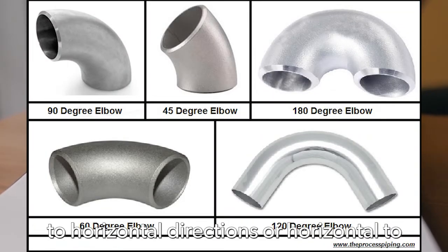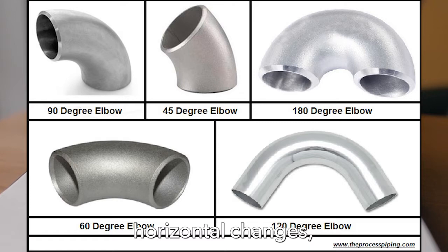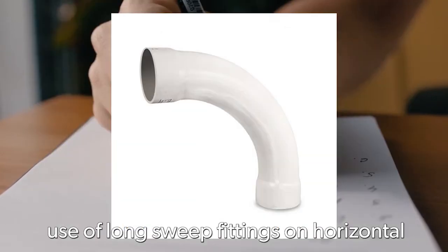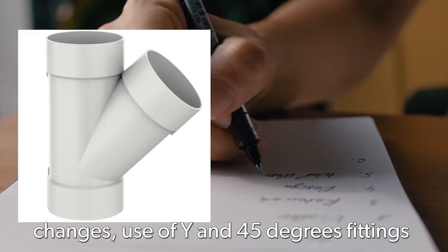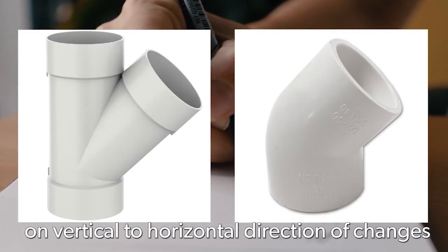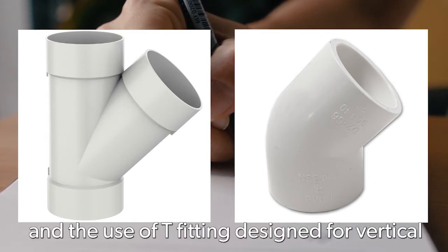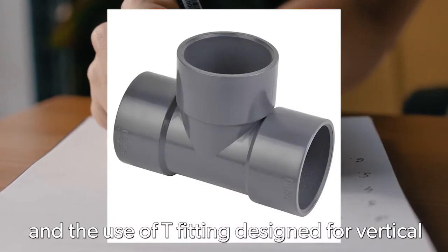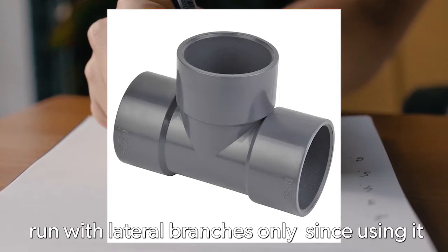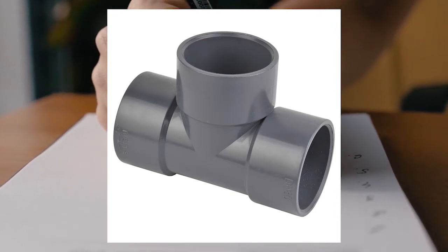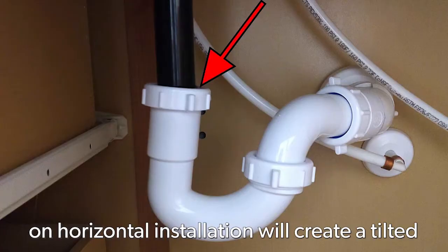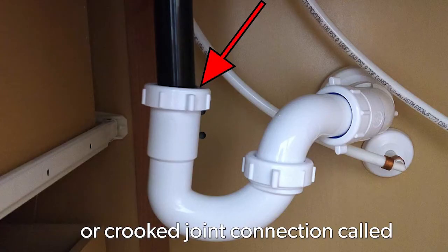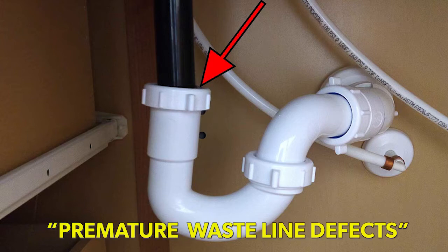horizontal directions or horizontal to horizontal changes, use of long sweep fittings on horizontal changes, use of Y and 45-degree fittings on vertical to horizontal direction of changes, and the use of T-fitting design for vertical run with lateral branches only, since using it on horizontal installation will create a tilted or crook joint connection called premature wasteline defects.